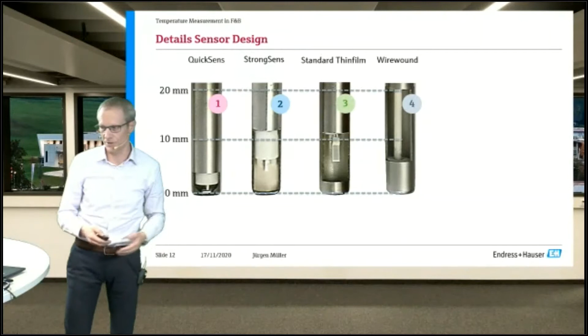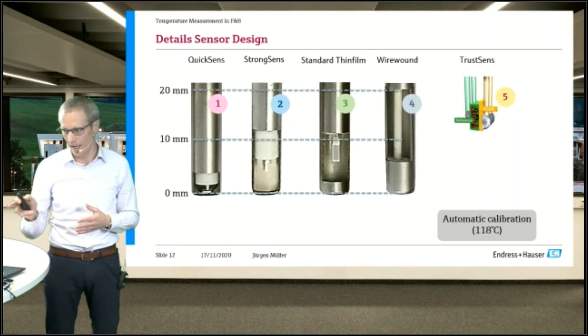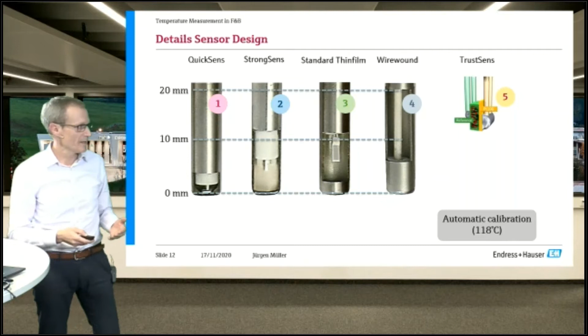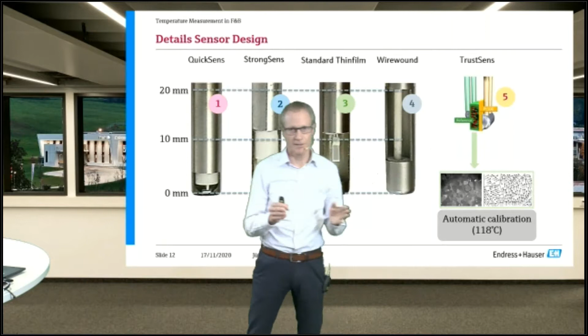sensor that only we from Endress and Hauser can offer. It is the TrustSens. This sensor does an automatic calibration at 118 degrees. Now, how is that possible? You see, we have a reference material that is in touch with the PT100 sensor itself. And whenever the 118 degrees are reached, this reference material triggers a calibration, an automatic calibration. And you don't need to worry about pressing a button or whatever. It just starts and the calibration is done.